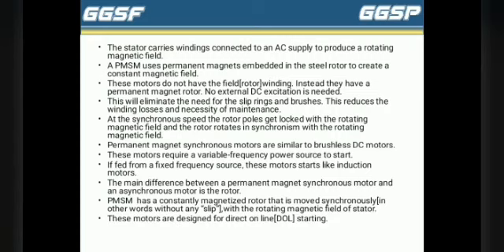These motors do not have a field, that is, a rotor winding. Instead, they have a permanent magnet rotor. No external DC excitation is needed. This will eliminate the need for the slip rings and brushes. This reduces the windage losses and the necessity of maintenance. At the synchronous speed, the rotor poles get locked with the rotating magnetic field and the rotor rotates in synchronism with the rotating magnetic field.